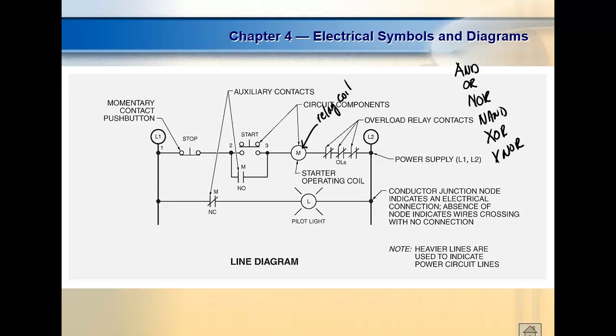Now we can have contacts controlled by that relay in our power circuit. In fact, I know it's a motor starter because of these guys right there. That tells me that relay runs a motor. As soon as I see those contacts, I know that relay runs a motor. That needs overloads. A lot of times your overloads are built into the motor, especially on your house. So just about all motors, up to very, very low fractional horsepower motors, you have to have an overload. So your motors in your HVAC system, your motors on your washing machine, your dryer, all have an overload, but they're integrated into the device itself.